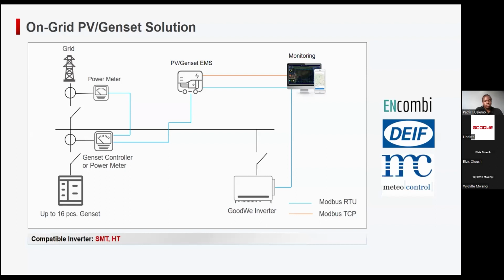You connect our on-grid inverters to the third-party hybrid controller, and through this, the inverters can work with the hybrid controller to minimize the consumption from the grid. And once the grid fails and the generator kicks in, the inverters are able to work with the third-party hybrid controller to reduce the fuel consumption of your generator, therefore minimizing the costs of energy consumption for the PV installation done.